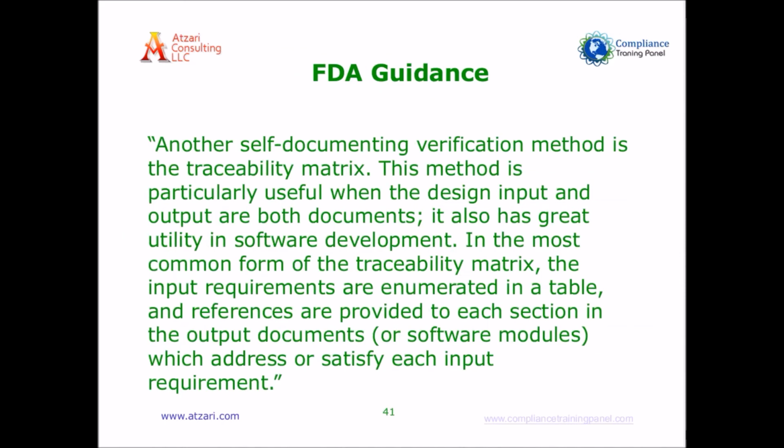Specifically, where it mentions the traceability matrix, now they're not telling you you have to have one, but think of it as an 800-pound hint. They're looking for that. They want to see it, but don't do it for them. Do it for you so that you can make sense of your requirements and your design. So it's a self-documented verification method, and it's particularly useful when the design input and output are both documents.